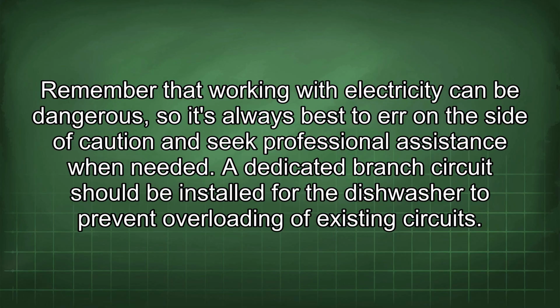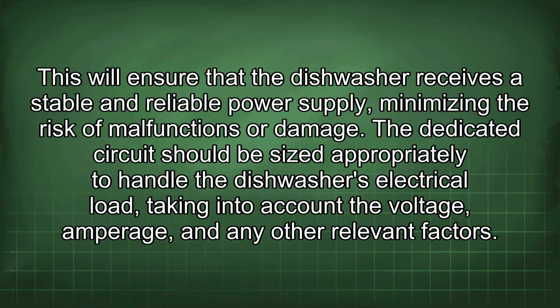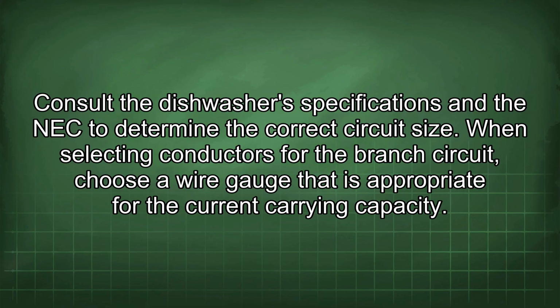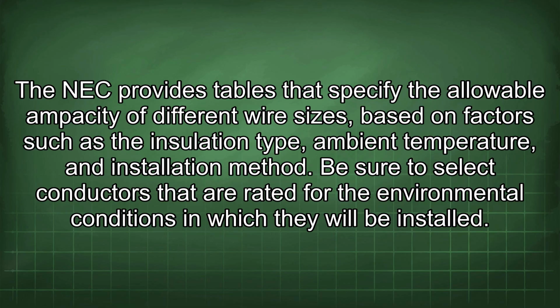A dedicated branch circuit should be installed for the dishwasher to prevent overloading of existing circuits. This will ensure that the dishwasher receives a stable and reliable power supply, minimizing the risk of malfunctions or damage. The dedicated circuit should be sized appropriately to handle the dishwasher's electrical load, taking into account the voltage, amperage, and any other relevant factors. Consult the dishwasher's specifications and the NEC to determine the correct circuit size. When selecting conductors for the branch circuit, choose a wire gauge that is appropriate for the current carrying capacity. The NEC provides tables that specify the allowable ampacity of different wire sizes based on factors such as the insulation type, ambient temperature, and installation method.